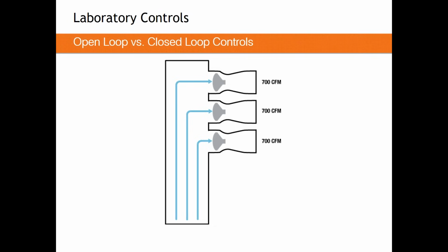Now, for the Venturi valve, consider that same application. And basically what we're doing here is comparing open loop versus closed loop controls. Say you have those 3 fume hoods hooked up to the same manifold again, and you close that middle fume hood down. What's going to happen again is instantaneously your system pressure will increase. However, the other 2 valves in that system will not change airflow whatsoever.